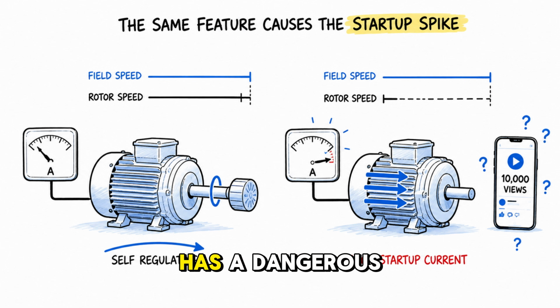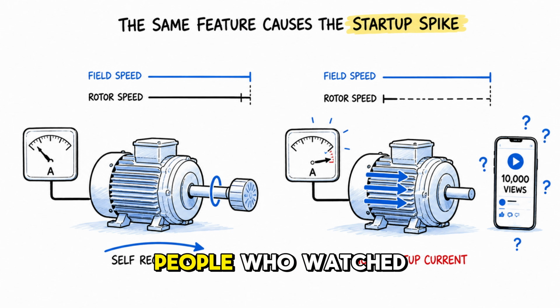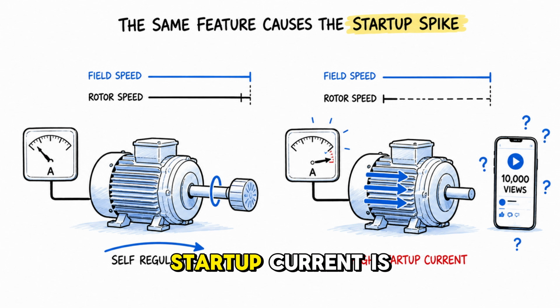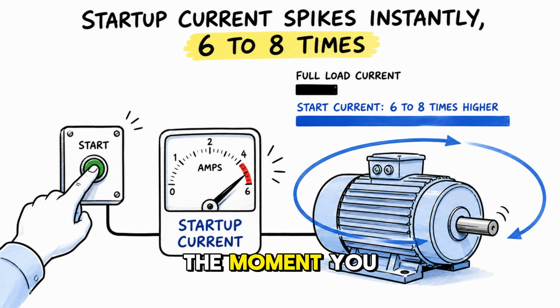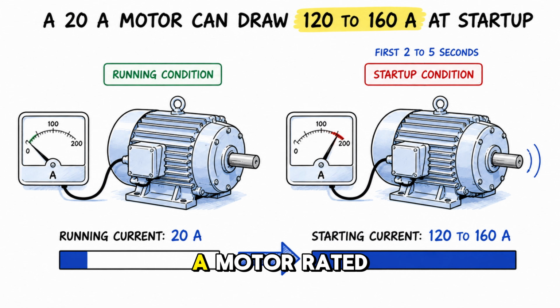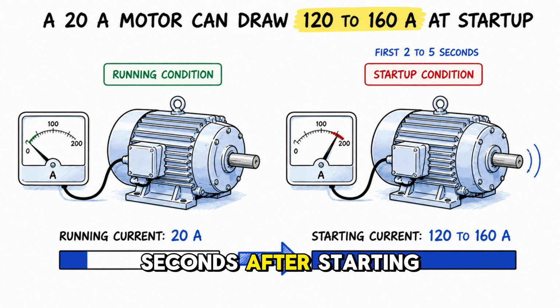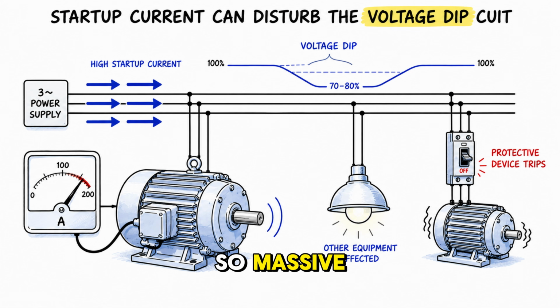But this self-regulation has a dangerous side effect at startup. And this is exactly what causes the 10,000 people who watched that short to ask why startup current is so high. The moment you press the start button on an induction motor, the current drawn from the supply spikes to 6 to 8 times the full load running current. A motor rated at 20 amperes running current will draw 120 to 160 amperes for the first 2 to 5 seconds after starting. This spike is so massive that it causes sudden voltage dips in the supply network. It can even trip protective devices on other equipment sharing the same electrical circuit.